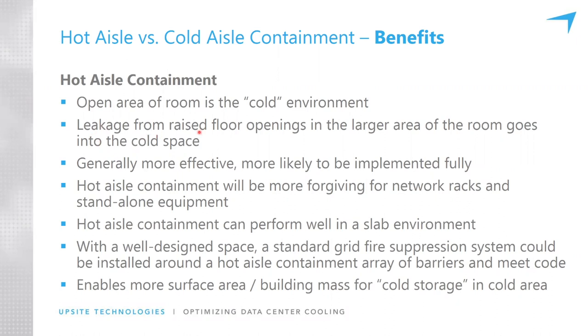When you're doing hot aisle containment, any leakage from the raised floor, misplaced supply tiles, leakage under electrical equipment, all that leakage just enters the cold space and is potentially available to cool IT equipment. It can flow through the room, and tile placement is not as critical. It's generally more effective because it's easier to implement fully, primarily for that reason: when you do cold aisle containment, the rest of the room becomes hot. Hot aisle containment will be more forgiving for the racks and the standalone equipment. This is really important for networking equipment that doesn't necessarily sit in a hot and cold aisle configuration. The open space is cold, and so you can place equipment anywhere in that space and it'll have some cooling.